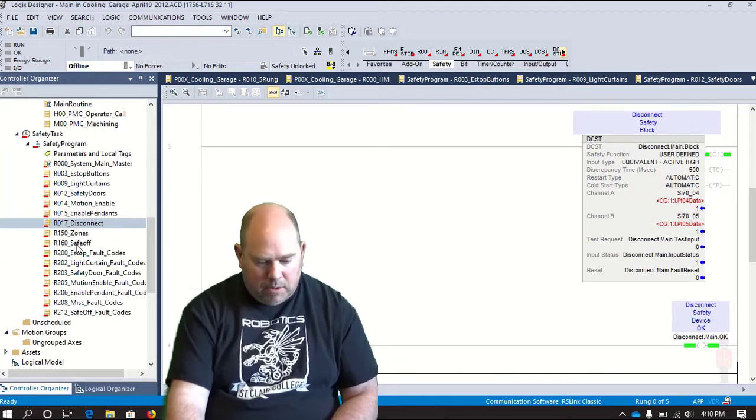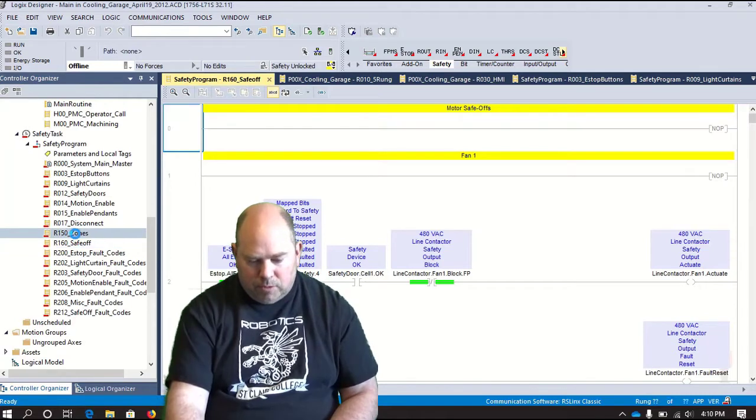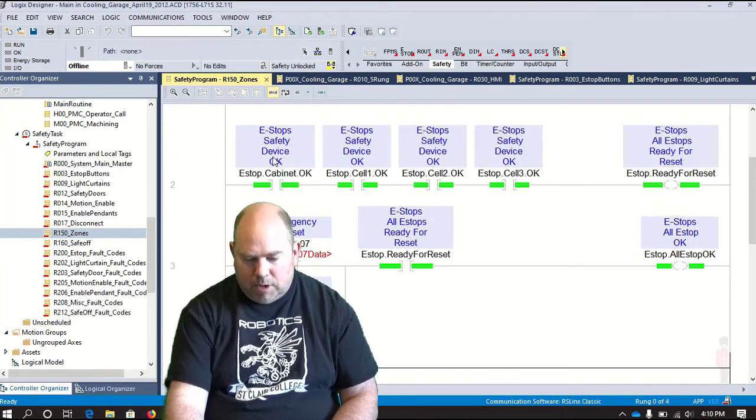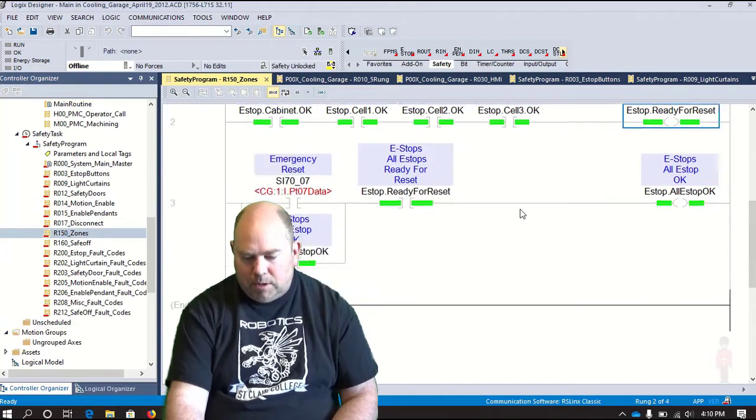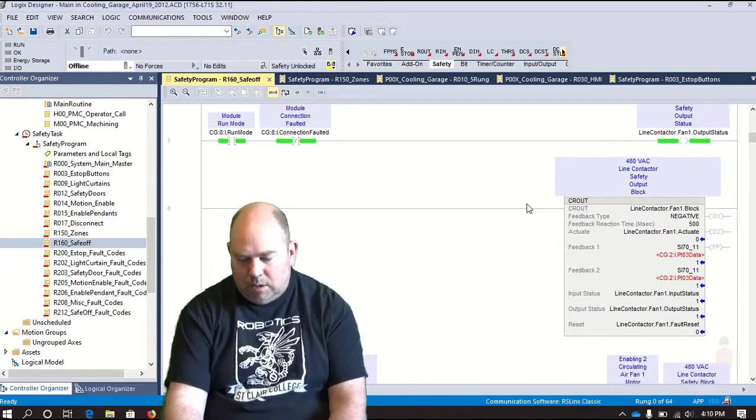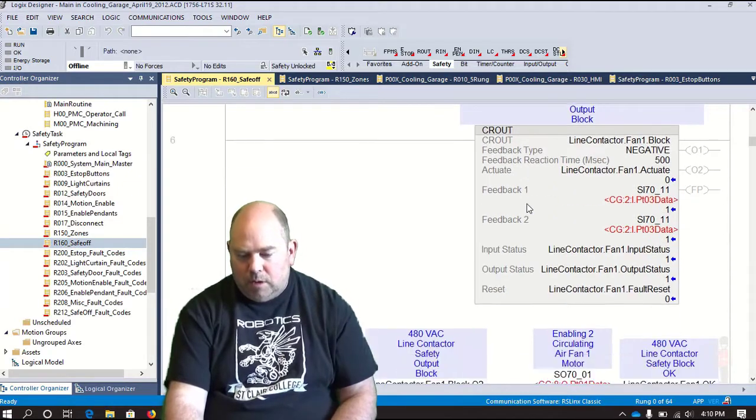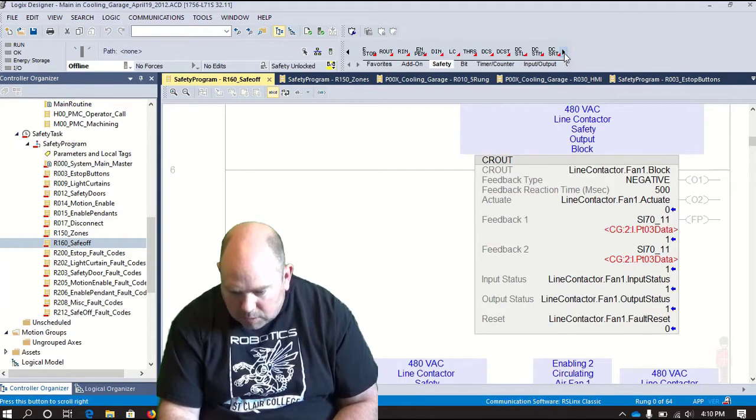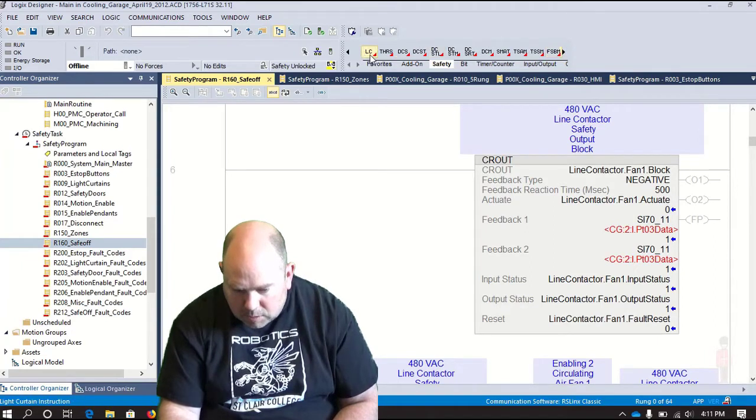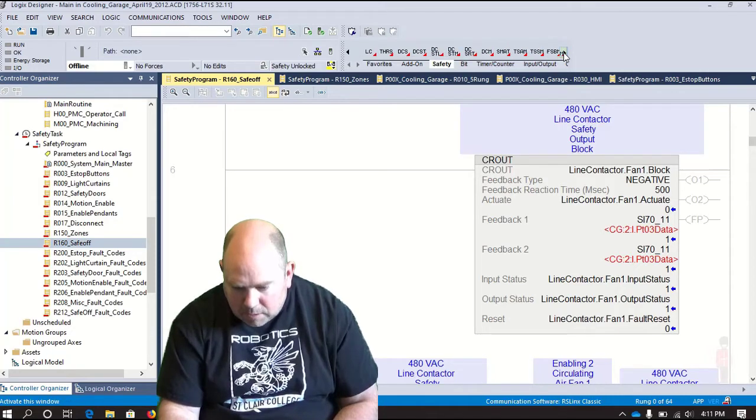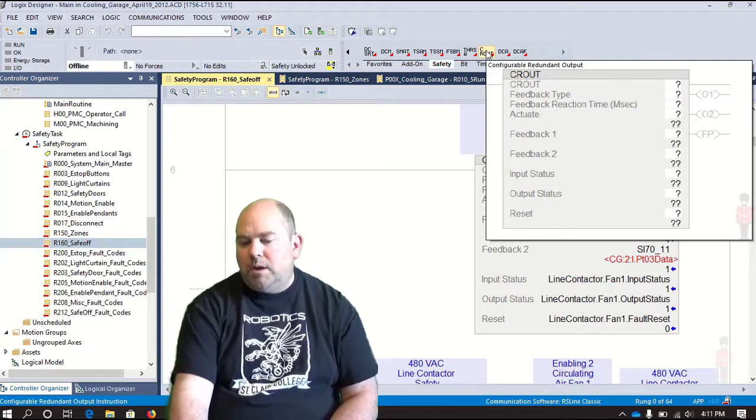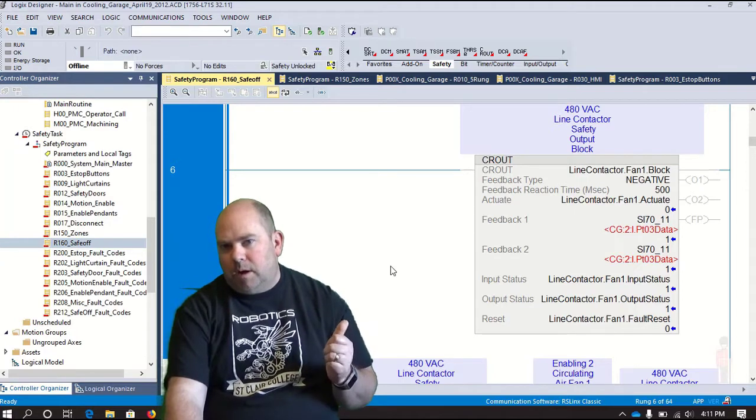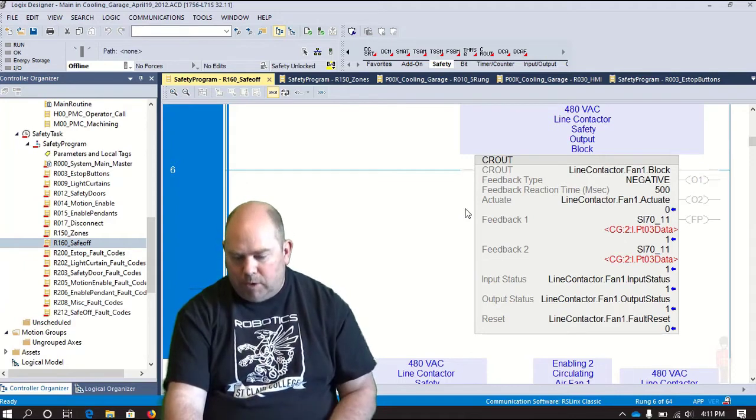And then on our outputs, these safe-offs were our outputs. So actually look at the zones first. Zones, pretty straightforward. All we had here was e-stops. One, two, three, e-stops, ready for reset. And then for safe-offs, which is our outputs, we're using this CR-OUT. And CR-OUT stands for, that's an output instruction here. Let's see what that stands for here. Configurable redundant output.